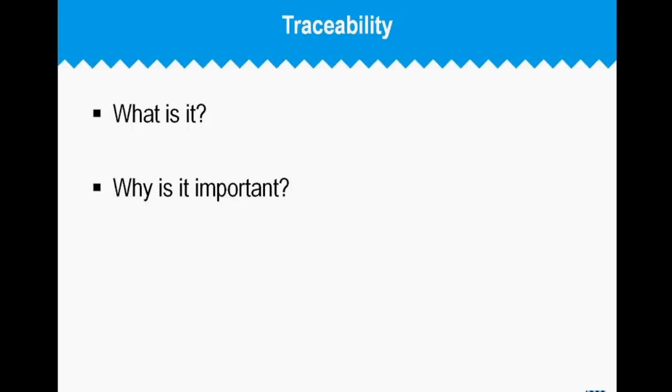It reminds me of the communication law. What was it? What's the law about how many links of communication you have back and forth with the number of people? What gets unmanageable is the number of connections of your requirements to your detailed design and on down to your code. So it's so important to know that with a change in the future, how it's going to impact the design and the integrity of the design, you need a full-fledged traceability matrix. Like Griffin alluded to, you can do it many different ways. We all start maybe with index cards and Scotch tape and have these things connected on the wall somewhere in our office, or we have a spreadsheet, or we have a more sophisticated database to keep track of it. But the idea is that you connect requirements to detailed design and the associated tests, and then sometime in the future you're going to make a change, and you're going to be able to understand the impact of that change by going back and reviewing this traceability matrix.